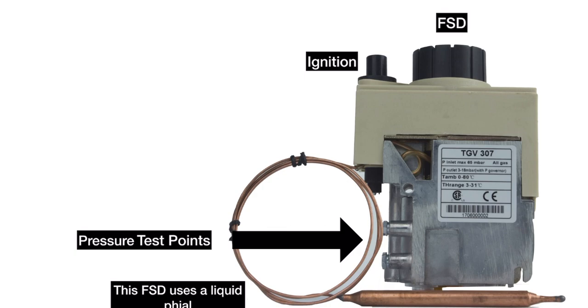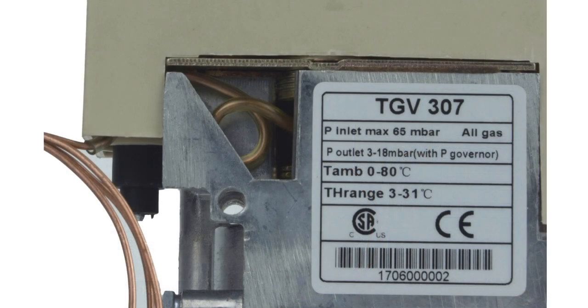And the pressure test points on this particular multifunction valve are those two, look like bolts sticking out. One, you put your U gauge on, and it's the inlet pressure, and the other is the burner pressure. If you look at the side of the valve, it actually tells you the maximum inlet pressure that this valve can take is 65 millibars. And the range of pressure outlet, which is the burner pressure, is between 3 and 18 millibars.